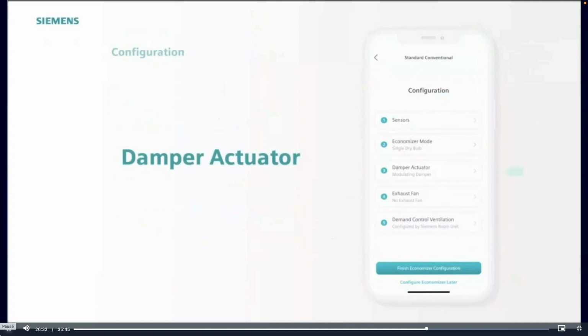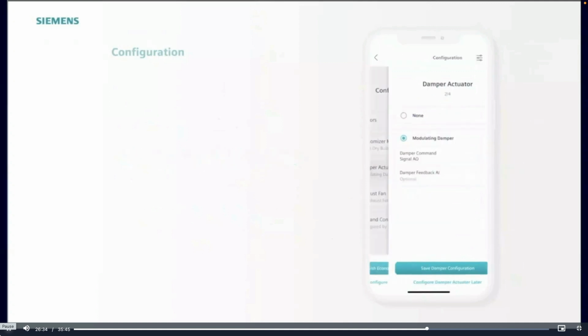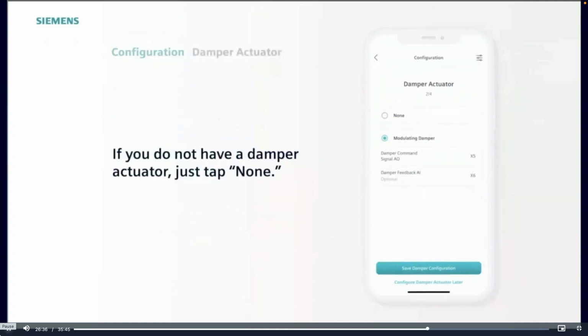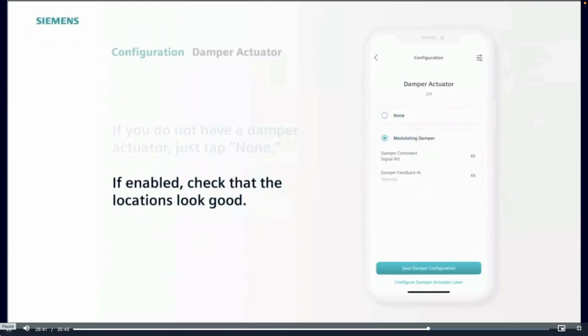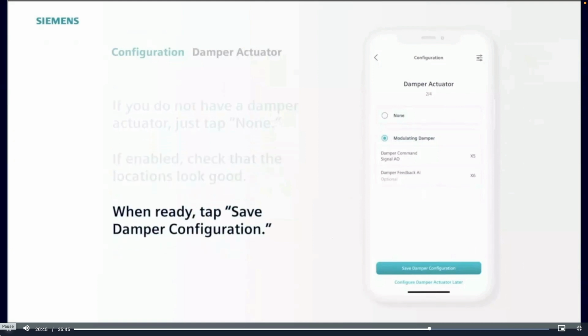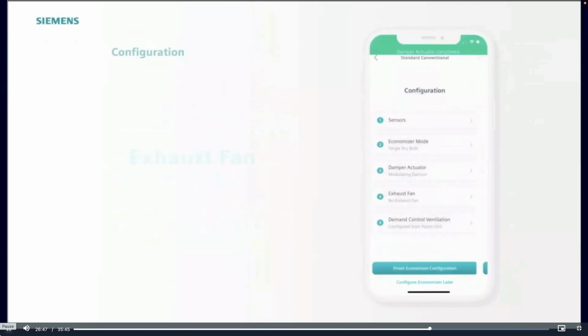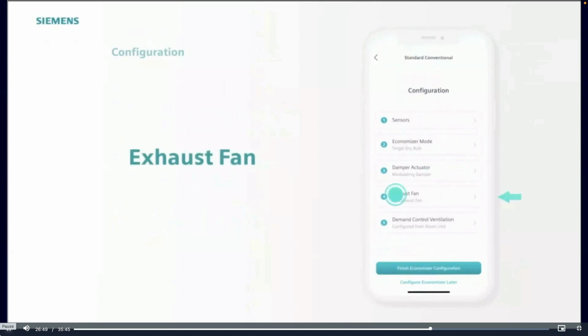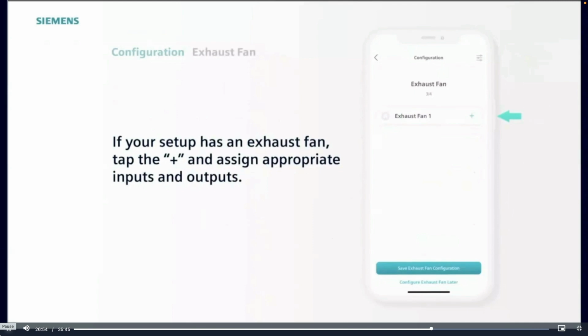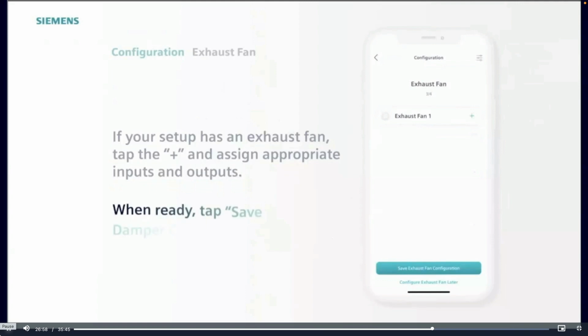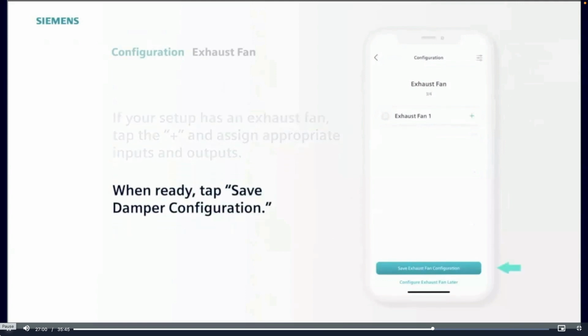Third is Damper Actuator. Tap to open. If you don't have a damper actuator, just tap None. For this example, we are using a modulating damper. With that selected, the preset locations look great, so this is all set. Tap Save Damper Configuration. Next is the exhaust fan. If your setup has an exhaust fan, you would add it using the plus symbol and then choose the appropriate inputs and outputs. For this example, we don't have an exhaust fan, so just tap Save Exhaust Fan Configuration and move on to number 5.